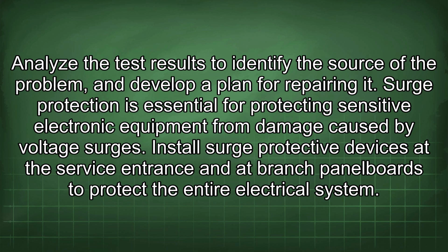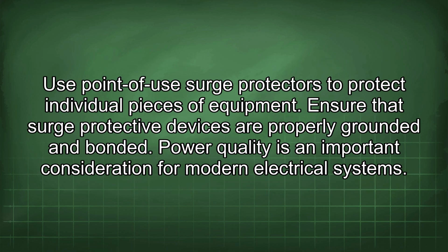Surge protection is essential for protecting sensitive electronic equipment from damage caused by voltage surges. Install surge protective devices at the service entrance and the branch panel boards to protect the entire electrical system. Use point-of-use surge protectors to protect individual pieces of equipment. Ensure that surge protective devices are properly grounded and bonded.